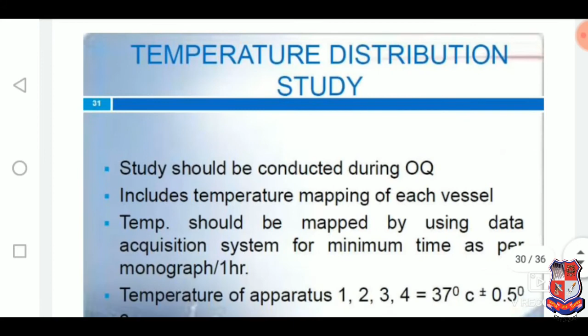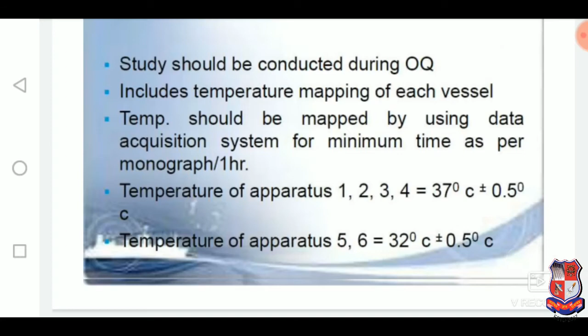Temperature distribution study should be conducted during operation qualification. It includes temperature mapping of each vessel. Temperature should be mapped using a data acquisition system for the minimum time as per the monograph. The temperature of the apparatus 1, 2, 3, 4 should be 37, that is the ideal, plus or minus 0.5. Temperature of the apparatus 5 or 6 is 32 degrees centigrade plus or minus 0.5 degrees. This is the temperature distribution study of the equipment during the operation qualification.